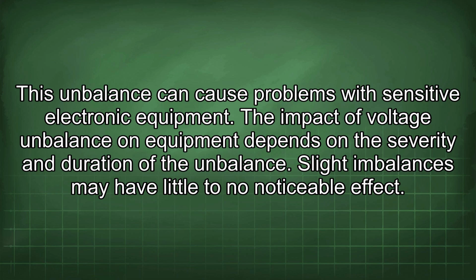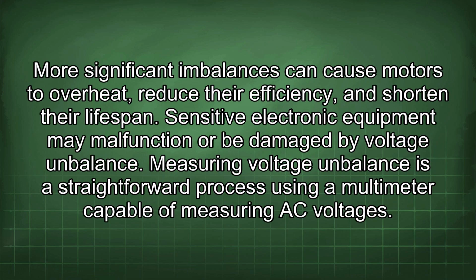The impact of voltage imbalance on equipment depends on the severity and duration of the imbalance. Slight imbalances may have little to no noticeable effect. More significant imbalances can cause motors to overheat, reduce their efficiency, and shorten their lifespan. Sensitive electronic equipment may malfunction or be damaged by voltage imbalance.